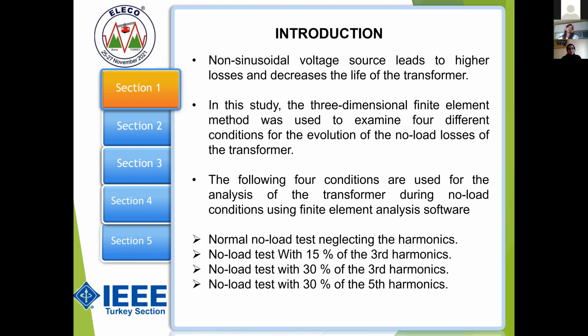In the first condition, we calculated the no-load losses without any harmonics. We also did the experimental work on that. In the second condition, we added 15% of the third harmonic. In the third condition, we added 30% of the third harmonic. And in the last condition, we added 30% of the fifth harmonic. As we know, with an increase in the percentage of the harmonics, the no-load loss also increases. But we don't know how much it is and how the third and fifth harmonics differ from each other if we use the same percentage.